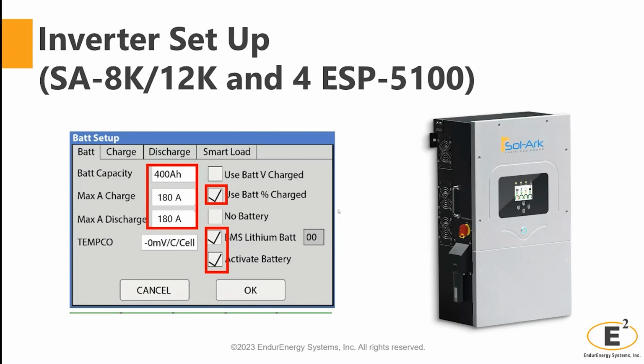Something you need to configure in the battery setup is the maximum charge amperage and maximum discharge amperage that the solar inverter needs to use for the batteries. In this case, we have a setup for 4 ESP 5100s using a Sol-Ark 8K or 12K. If you multiply the 60 amps we can sustain per battery times 4, that gives you 240 amps. The 8K and 12K have an amperage limit of 180 amps of charge and discharge for the battery bank, so you need to make sure the max amperage charge and discharge is set to those values.